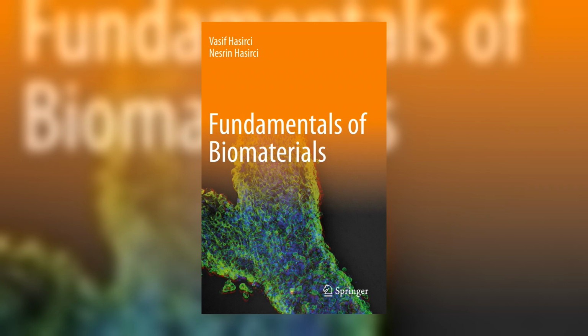10993, Part 9, the framework for identifying and quantifying potential degradation products. Part 9 is an abstract contract rather than a test. It fixes how you would identify and count whatever a biomaterial breaks into before any material-specific method exists. The concrete parts are its implementations, Part 13 for polymers, Part 14 for ceramics, Part 15 for metals. Part 9 is the interface they all satisfy.